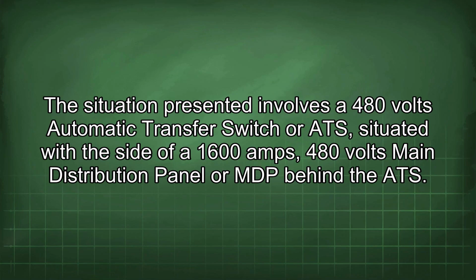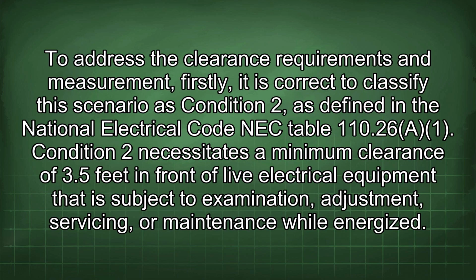The situation presented involves a 480 volts automatic transfer switch, or ATS, situated beside a 1600 amps, 480 volts main distribution panel, or MDP, behind the ATS. To address the clearance requirements and measurement, firstly, it is correct to classify the scenario as Condition 2 as defined in the National Electrical Code, NEC Table 110.26(A)(1).